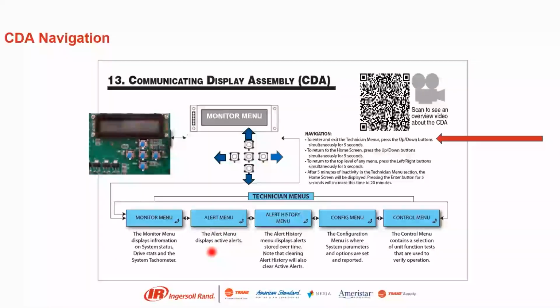It's going to show our alert menu, and that's going to have our active alerts. If we scroll one more right, so monitor menu is always going to show up first, our alert history menu. So we want to go through there and log what our alert history is. Configuration menu is where we can actually change some parameters. So we might want to go in there. I'm going to show you what to change in there, what we recommend, and then our control menu for testing. So we get into the control menu quite a bit.